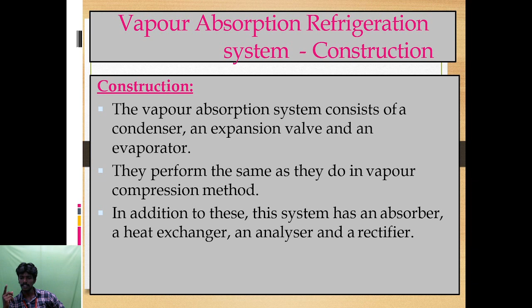Vapor absorption refrigeration system working principle. Dry ammonia vapor at low pressure passes into the absorber from the evaporator. In the absorber, the dry ammonia vapor is dissolved in cold water and a strong solution of ammonia is formed. I already told that the absorber contains cooling water flowing through a cooling coil. Water has a high affinity to ammonia, so it absorbs more ammonia. Then it moves to the generator.